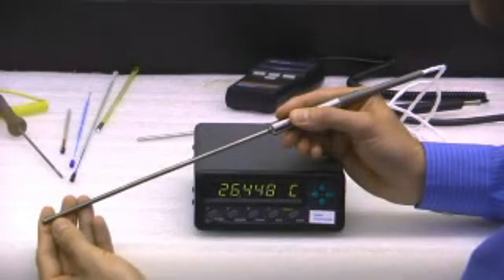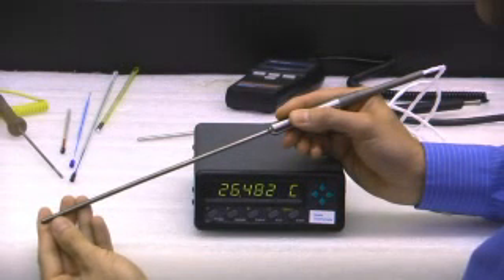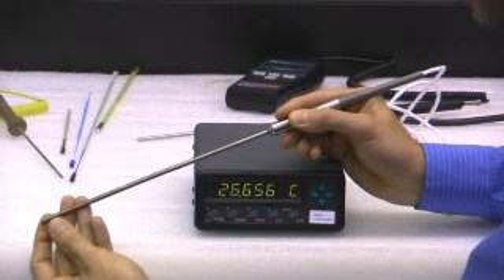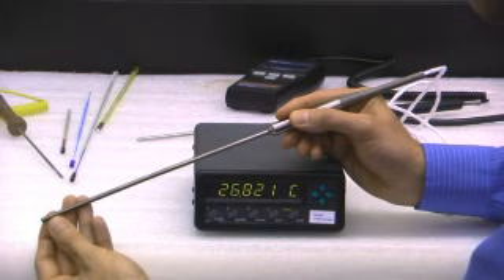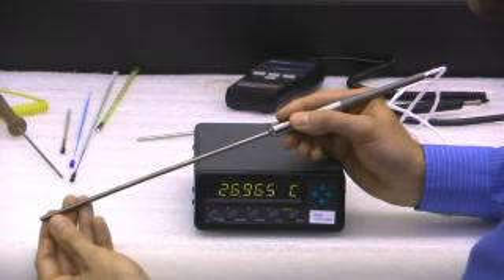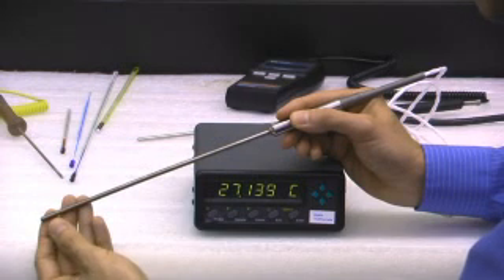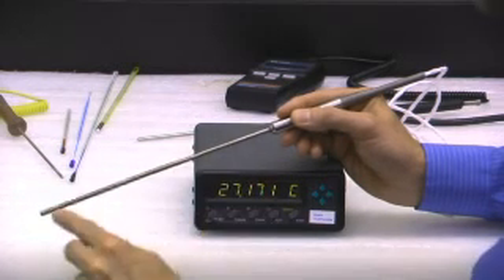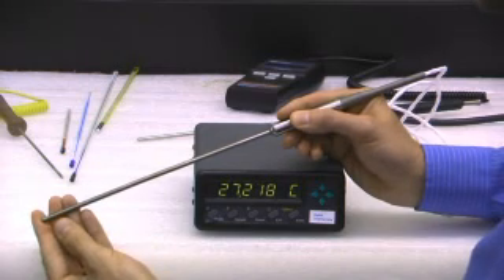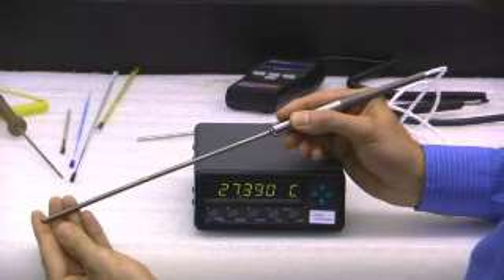The sensor at the tip of the probe is subject to damage if you hit it hard, if it's mechanically shocked. If that's a problem in your application, you can get PRT sensors that are made of thin films deposited on ceramics. Those are a good choice for harsh environments. Another type of sensor that also fits into a probe like this is a thermistor. A thermistor is a good choice in the temperature range from -20 to approximately 100 degrees Celsius, or about -4 degrees Fahrenheit to 212 degrees Fahrenheit.